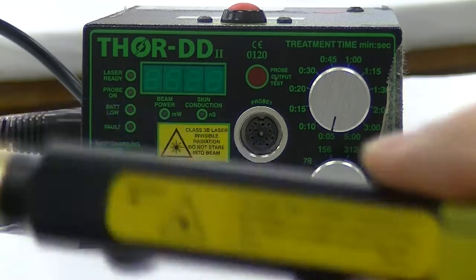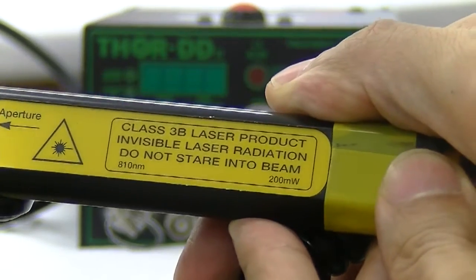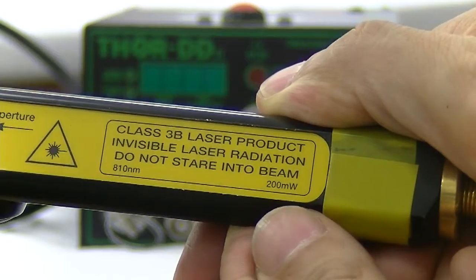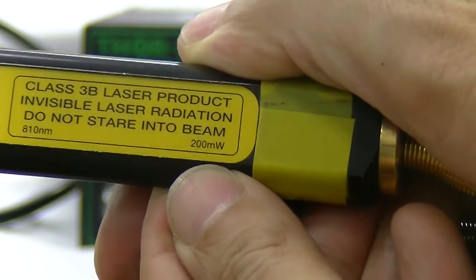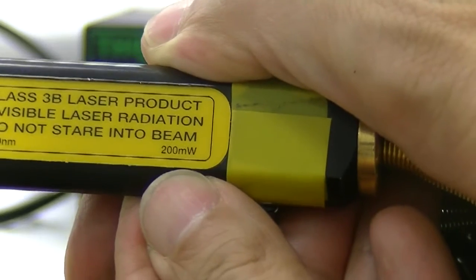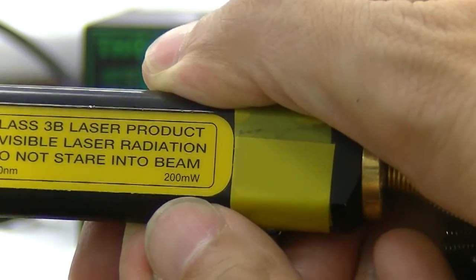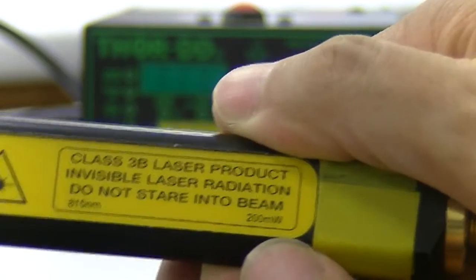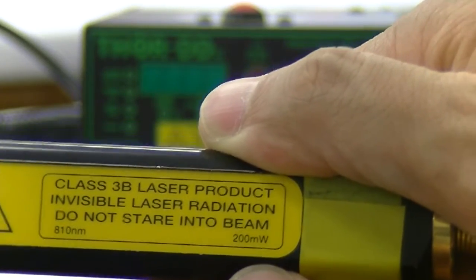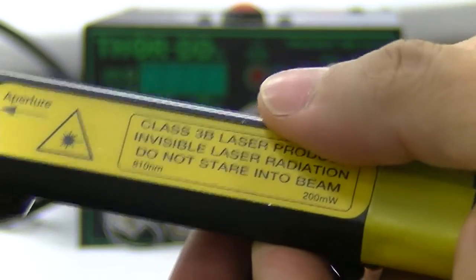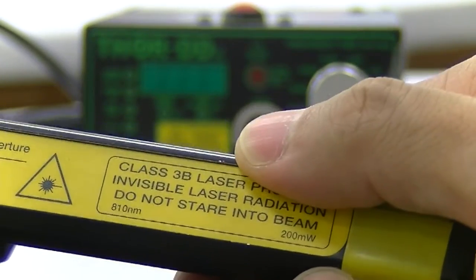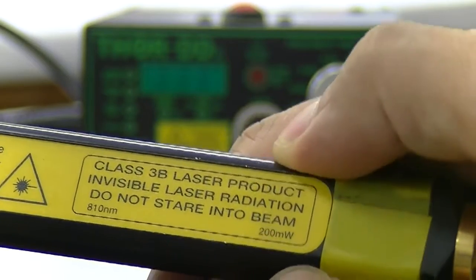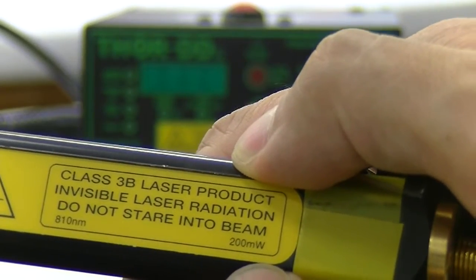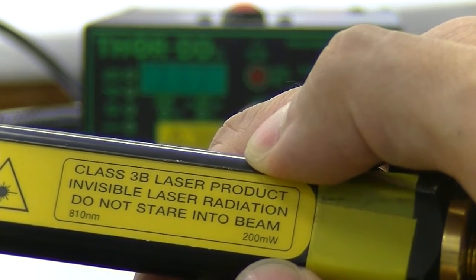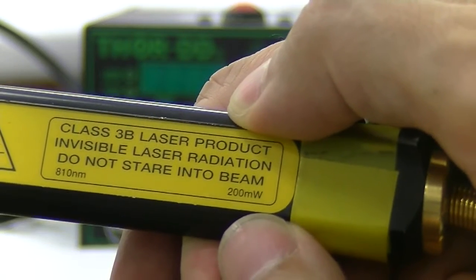Before I start, just look at this probe again. We have a series of different probes. Every time you need to do a treatment, before that you need to look at the power of the probe. So you see here, this one is a bit more powerful. This is 200 milliwatts. That means 0.2 watts, which means every single second it delivers 0.2 joule. So in case we have a treatment area that requires 2 joule per spot, for that case you need 10 seconds in order to deliver enough energy, because 2 divided by 0.2 is 10 seconds.